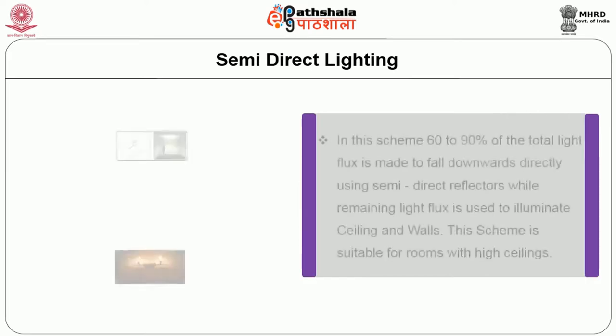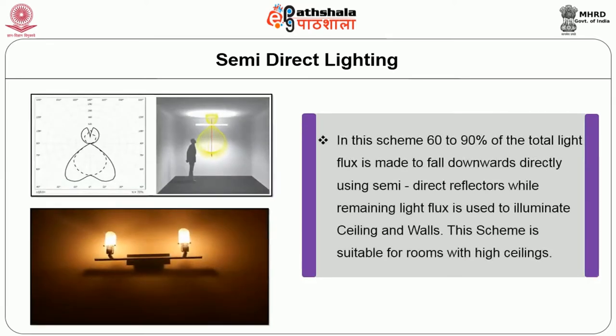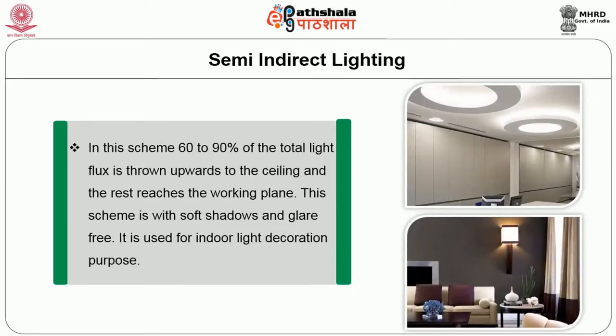Semi-direct lighting: in this scheme, 60 to 90% of total flux is made to fall downwards directly using semi-direct reflectors, while the remaining light flux is used to illuminate the ceiling and walls. This scheme is suitable for rooms with high ceilings. Semi-indirect lighting: in this scheme, 60 to 90% of the total light flux is thrown upwards to the ceiling and the rest reaches the working plane. This scheme has soft shadows and is glare-free, and is used for indoor lighting and decoration purposes.